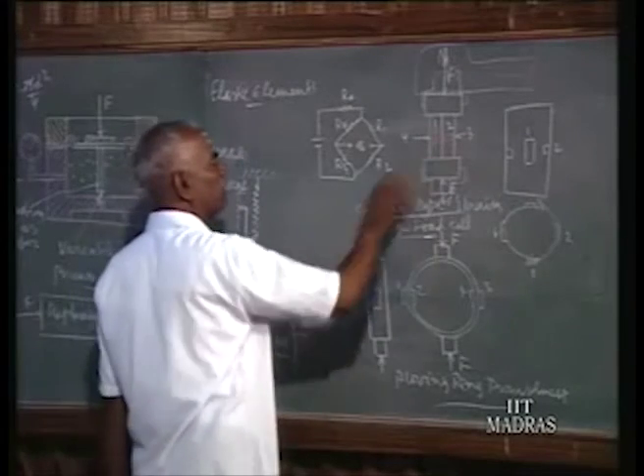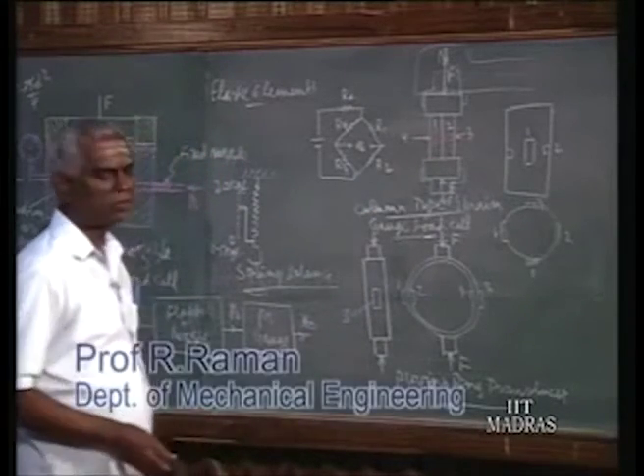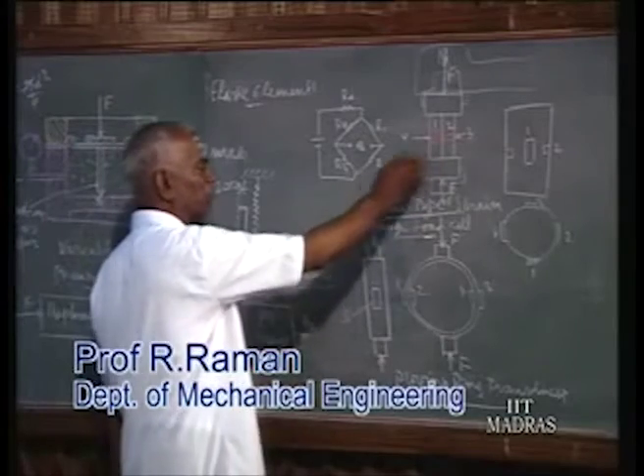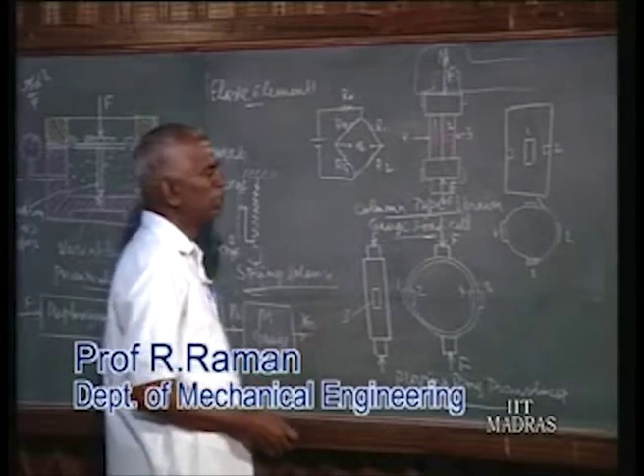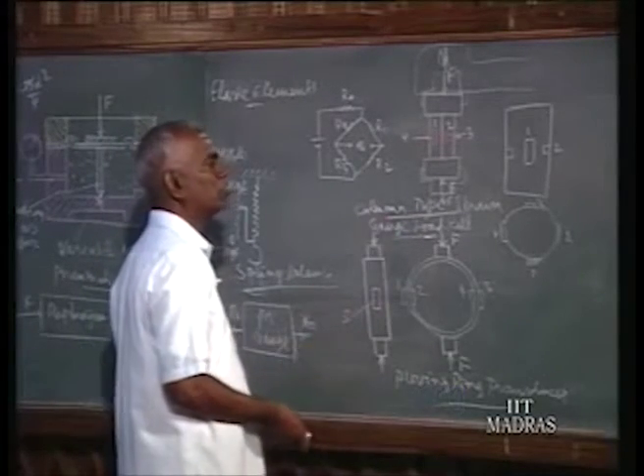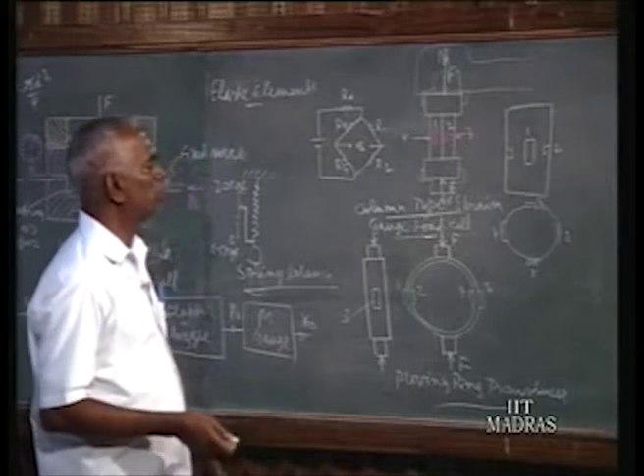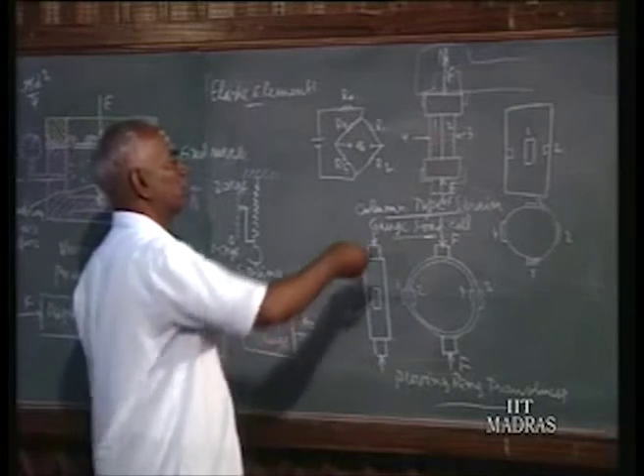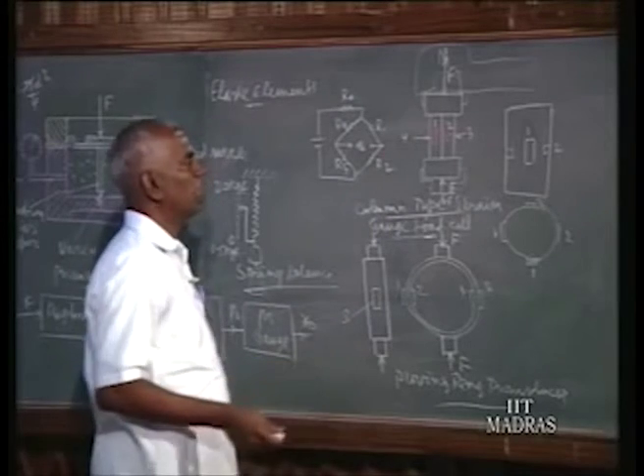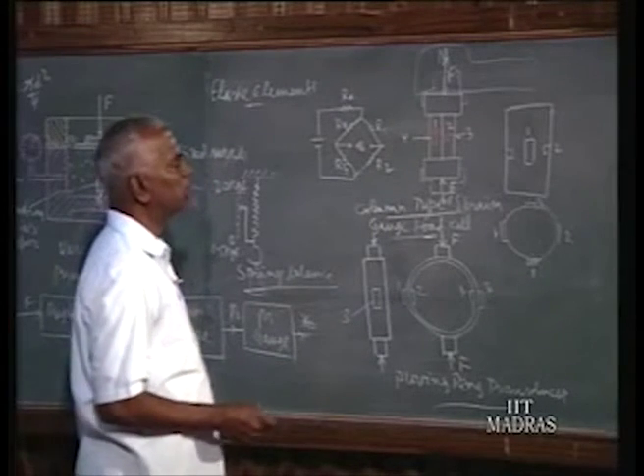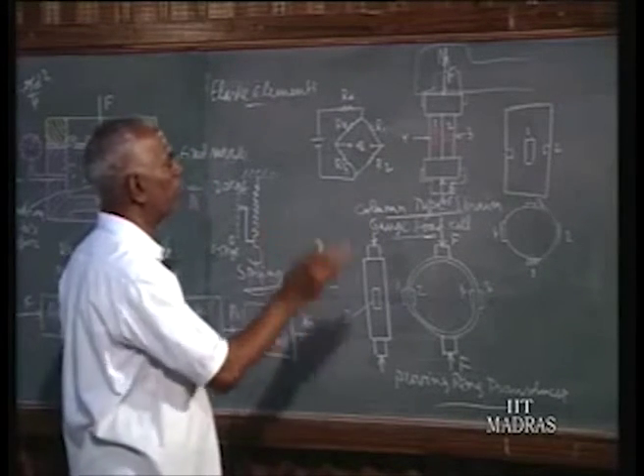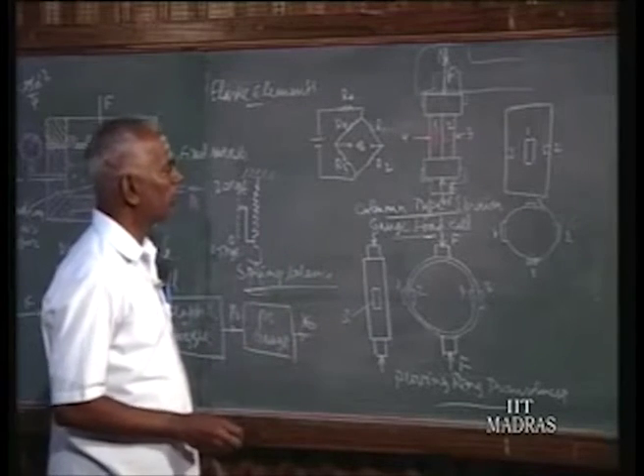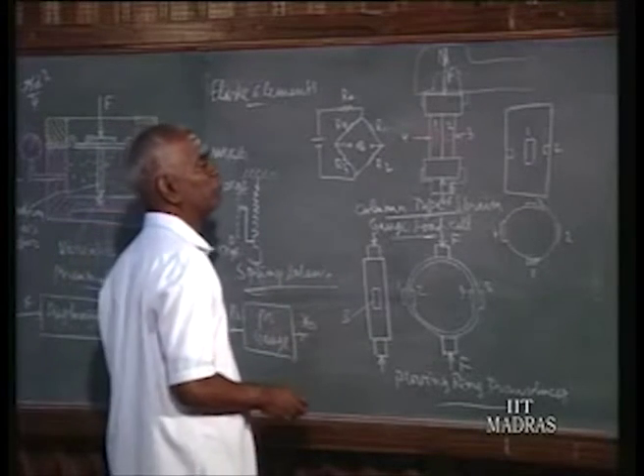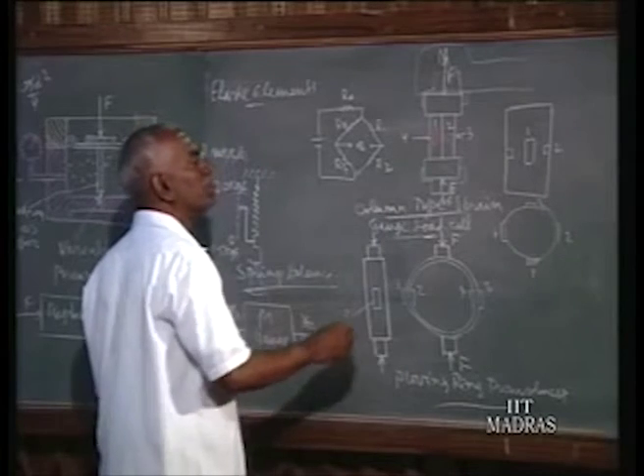And this column material you have to carefully select. We should reduce the hysteresis effect of the spring material. So some alloyed steel or spring steel with some additions will give a large elastic limit as well as less hysteresis. This is what is important for long time usage or long life. The calibration should not change.